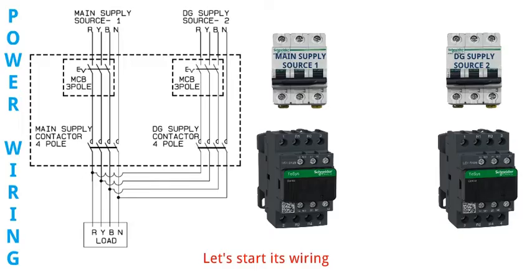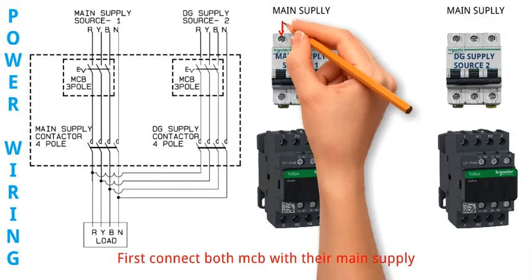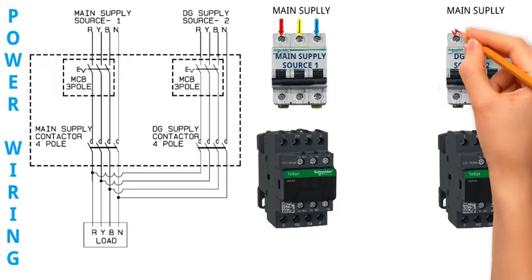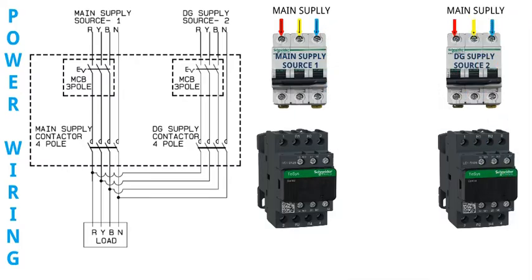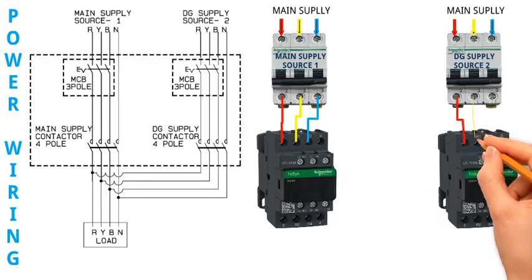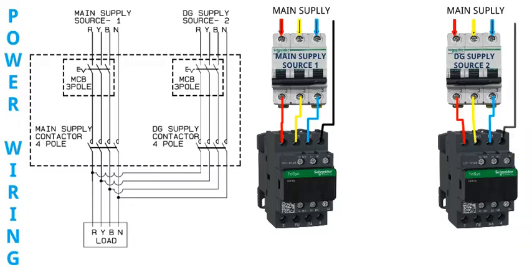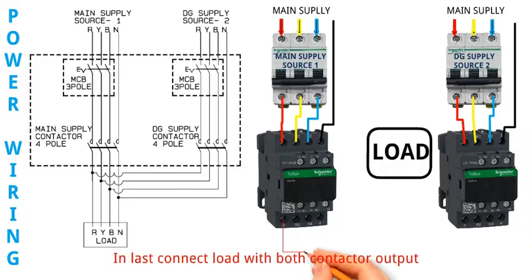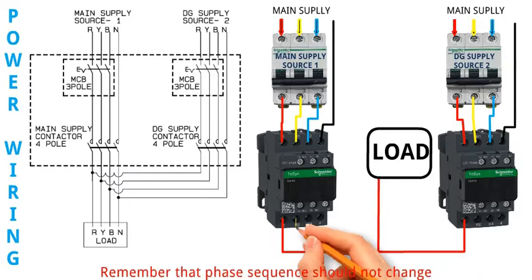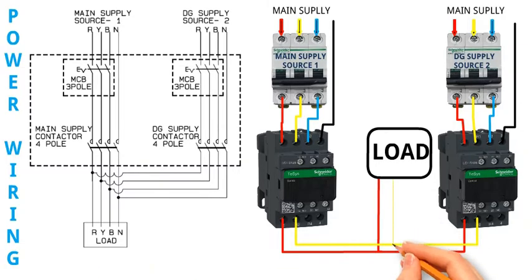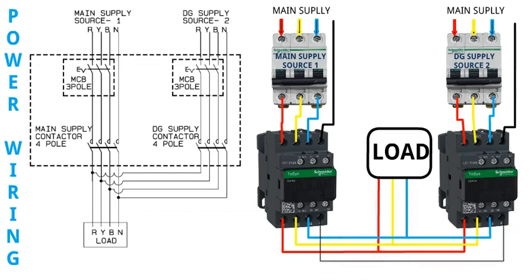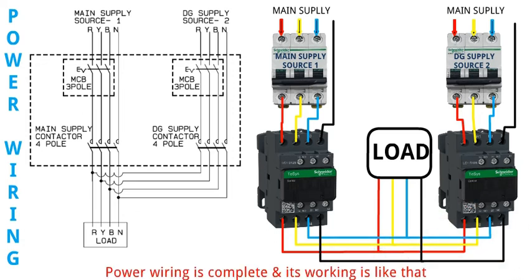Let's start its wiring. First connect both MCBs with their main supply. After that connect the MCB output with the contactor. Then connect neutral with the contactor. In last, connect the load with both contactor outputs. Remember that phase sequence should not change, and tape the connections properly.